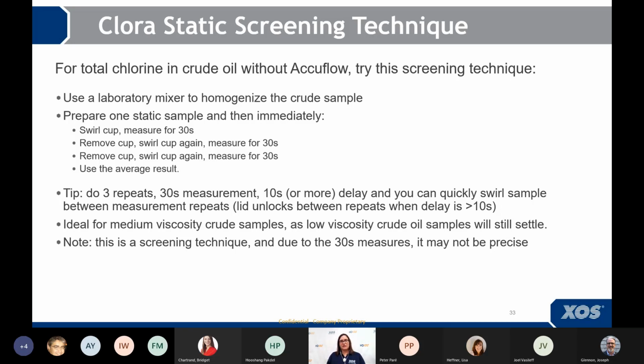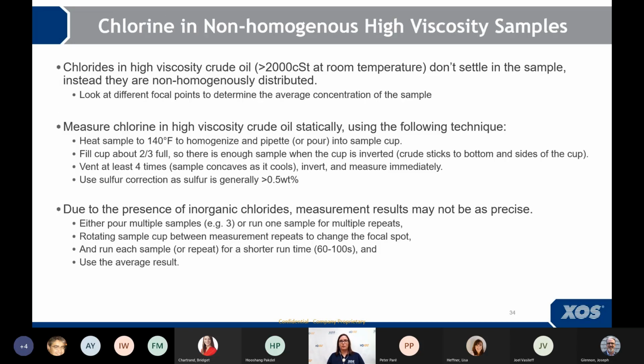But what about the other extreme, high viscosity samples? What do you do for chlorine in high viscosity samples? It's not settling because the samples are semi-solid or perhaps solid at room temperature, so it's not settling. But the problem is that the chlorine is non-homogeneously distributed. So when you measure it, it depends on where your focal point is, what chlorine you're seeing. So one of the things you can do here is that you look at different focal points in the sample, and then you take the average of that and this will tell you what's actually in there, rather than measuring one focal point several times. You get a better idea of what's actually in the cup if you look at the different focal points.